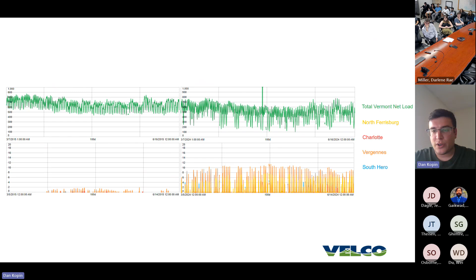This is a great slide from New England, ISO New England gets full credit for this. You're seeing what they're expecting to be the estimated reduction in net load from behind the meter PV. As that occurs, what is the true load at this particular time? That 12,000 megawatts, for the purposes of this diagram, is going down further and further over time. We're expecting within New England the same trend Vermont is experiencing. We have a true net load, or true gross load, that is at 12,000 megawatts, but as over time DG comes online, we're expecting to reach below 2,000 megawatts.